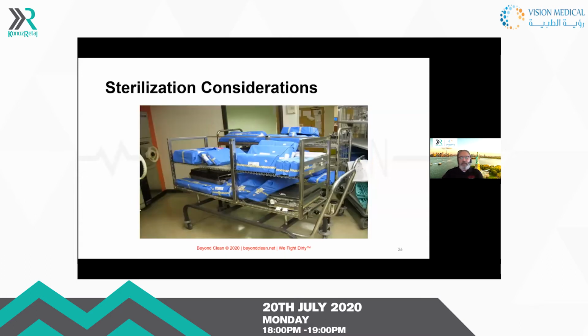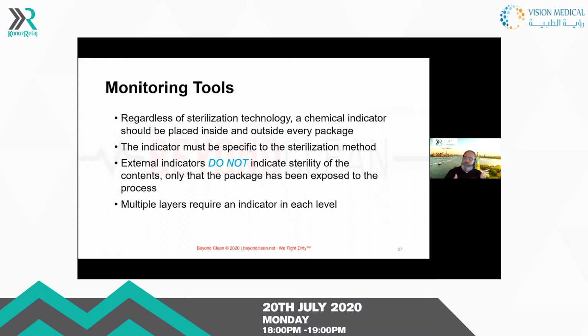When we sterilize these instruments, we want to make sure that we're packaging and loading the autoclave properly. Regardless of the technology, we want to make sure that we have chemical indicators and integrators on the outside for a visual inspection, but also on the inside to ensure that the sterilant has penetrated. External indicators do not indicate sterility, but they're very important to know that this product has come in contact with a device or a sterilization modality.